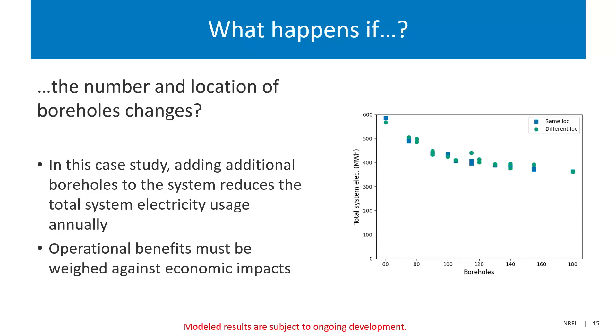As a final example, you can think about what happens as you change the number and location of boreholes around the loop. More boreholes means less energy is used — because you don't need an auxiliary electric boiler — but you have to weigh that against economic impacts: how much did the boreholes cost, and was that cost worth it? What does your trade-off look like there?